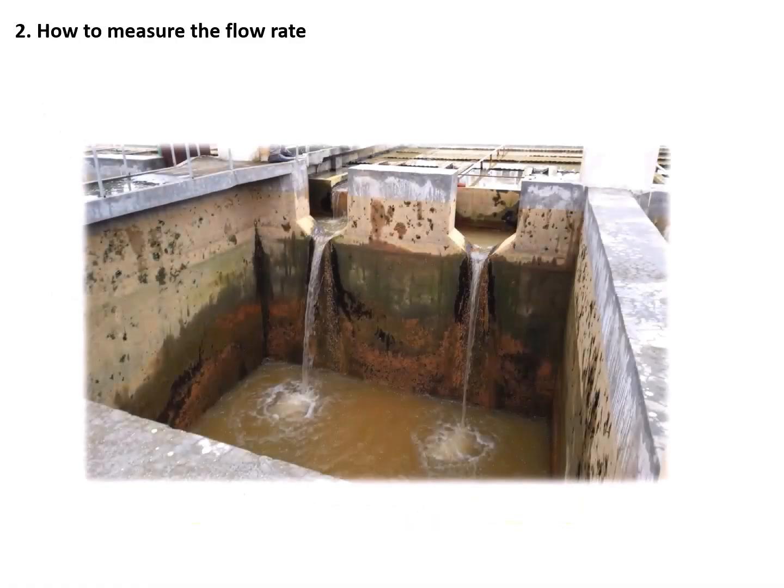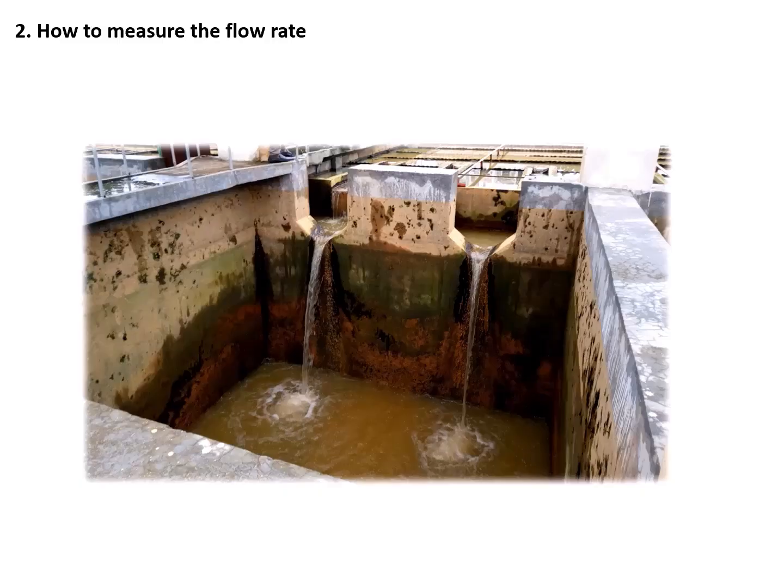It is possible to incorporate this methodology at a water treatment plant. Shut off the valve right after filtration so that water can be reserved in the basin. By observing the water level and time, the flow rate can be calculated. In most cases, several pumps are running simultaneously, and there are multiple filtration basins at the plant. To make it accurate, those conditions should be considered.